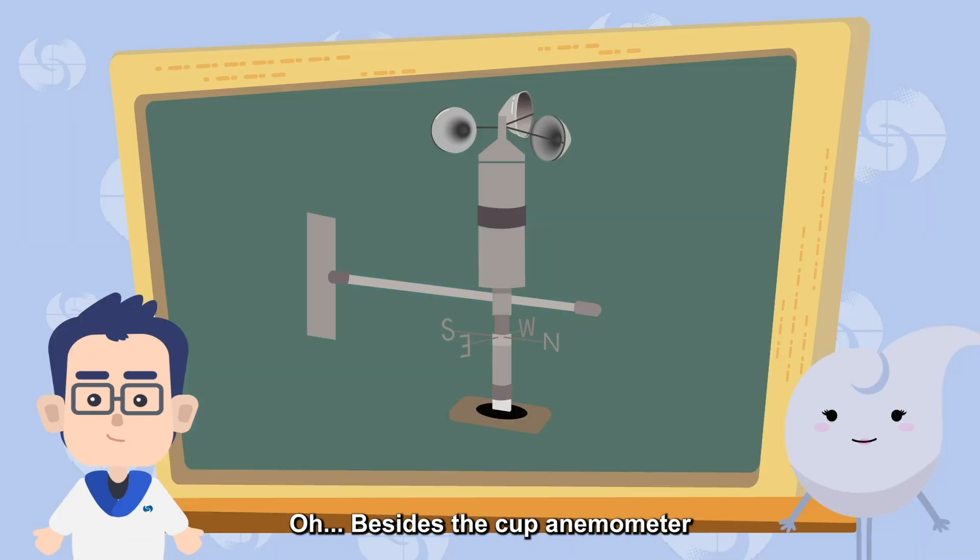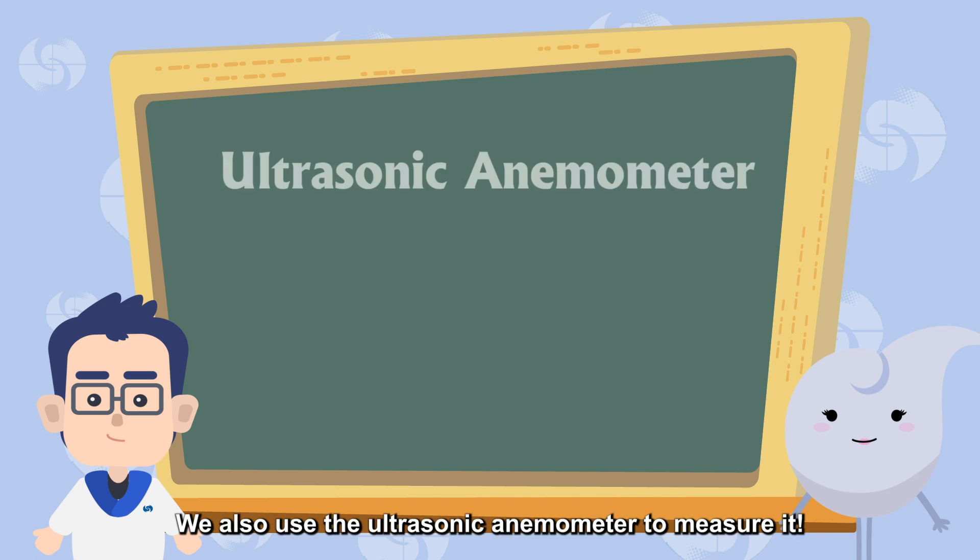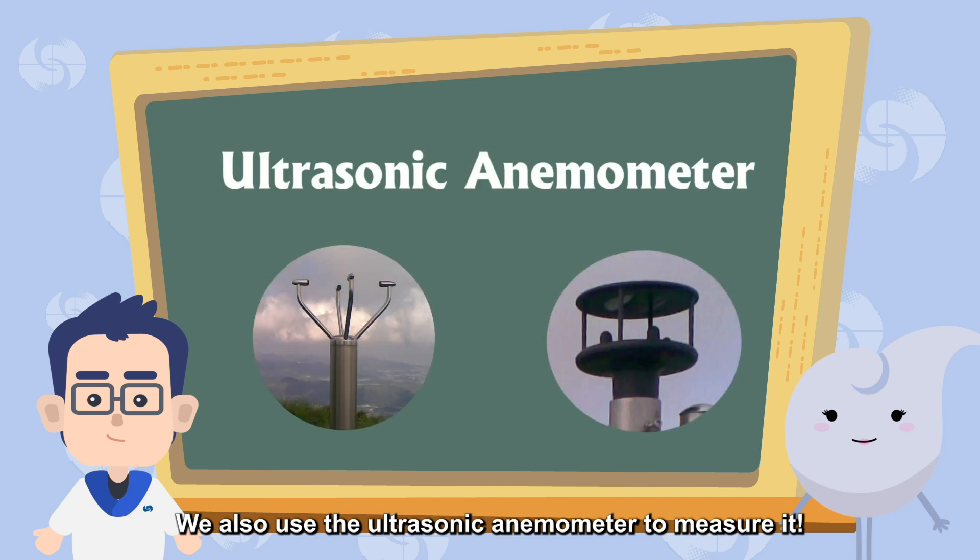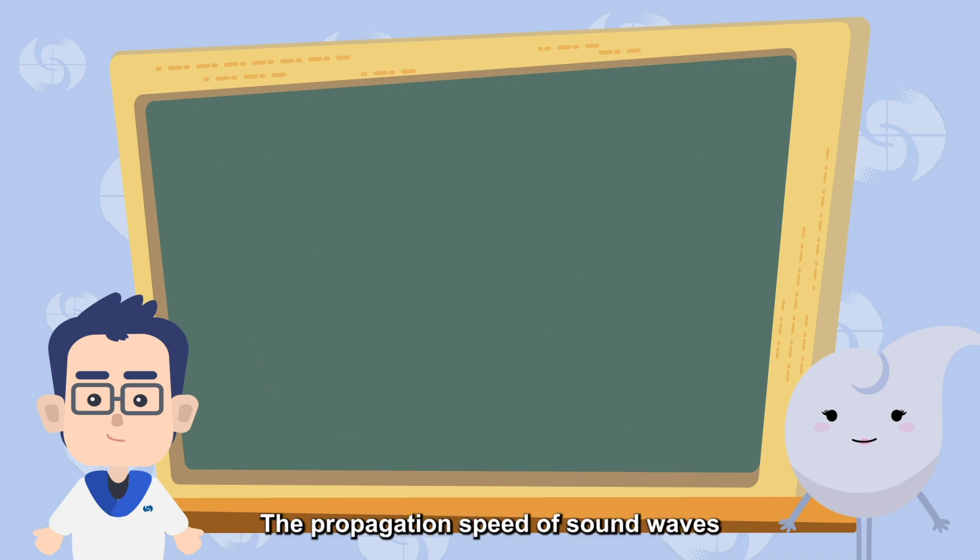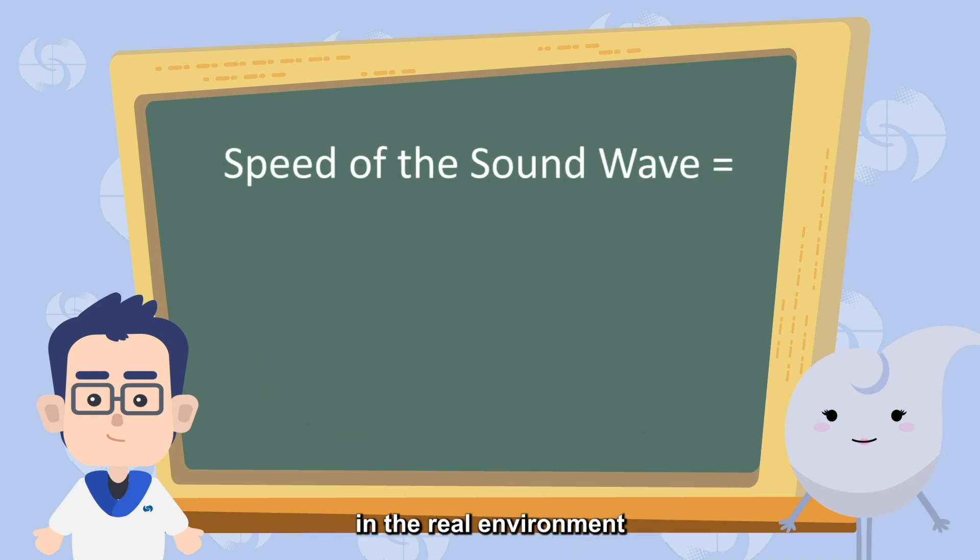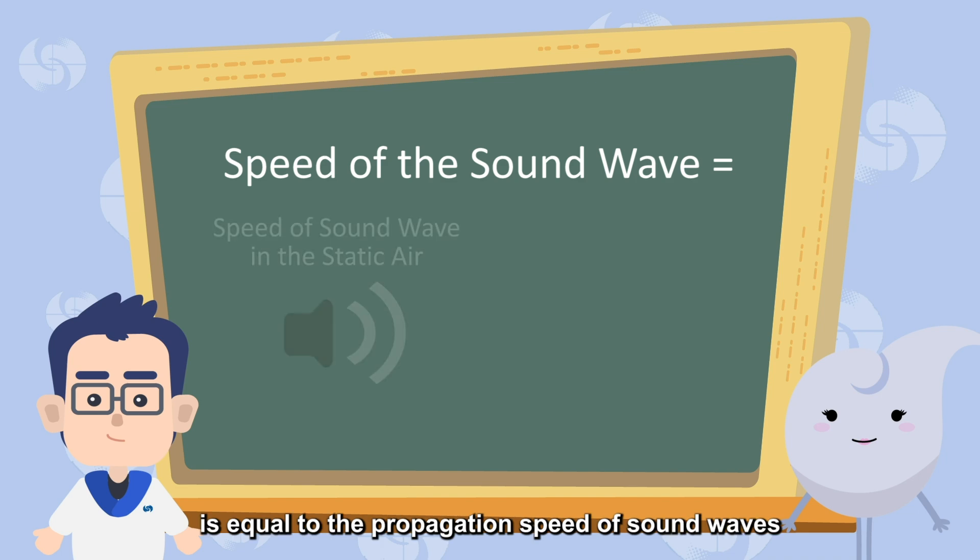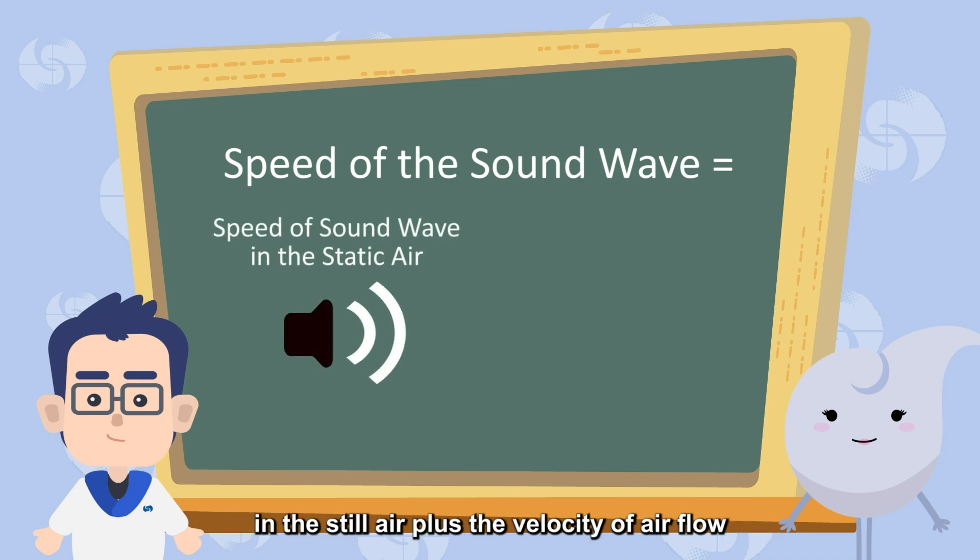Besides the cup anemometer, does the observatory use any other instruments to measure wind speed? We also use the ultrasonic anemometer to measure it. Ultrasonic anemometer? Yes. It uses the speed of sound waves to calculate wind speed. The propagation speed of sound waves in the real environment is equal to the propagation speed of sound waves in the still air plus the velocity of air flow in the atmosphere.